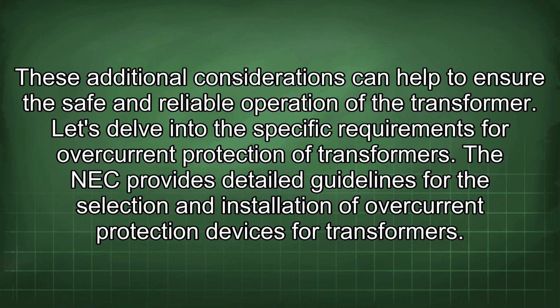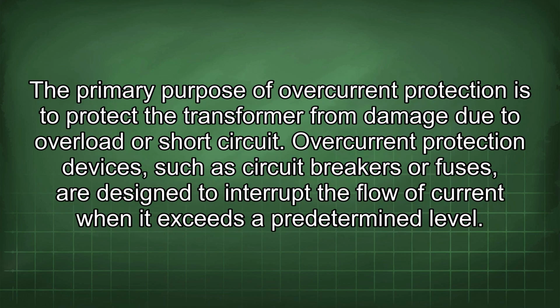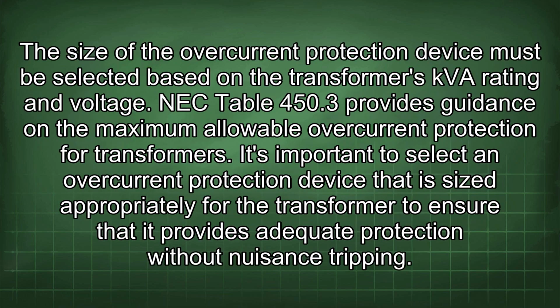The NEC provides detailed guidelines for the selection and installation of overcurrent protection devices for transformers. The primary purpose of overcurrent protection is to protect the transformer from damage due to overload or short circuits. Overcurrent protection devices, such as circuit breakers or fuses, are designed to interrupt the flow of current when it exceeds a predetermined level. The size of the overcurrent protection device must be selected based on the transformer's kVA rating and voltage. NEC Table 450.3 provides guidance on the maximum allowable overcurrent protection for transformers. It's important to select an overcurrent protection device that is sized appropriately for the transformer to ensure that it provides adequate protection without nuisance tripping.